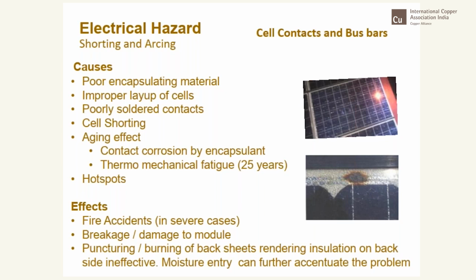In the first photograph, you can see that arcing is taking place within the module itself, and that could be disastrous. So, improper layup of cells: during the manufacturing phase, if the solar cells are not properly laid between the two layers of encapsulant, there is some mismatch or physical contact. And again, poor soldering. There are hundreds of cells, all of them soldered, and if there is any poor contact, it becomes a source of heat. If not immediately passed, the contact will degrade further and create more heat, and ultimately it will lead to fire accidents.